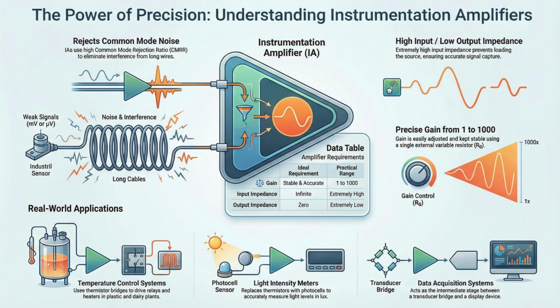And this is where your argument for survival over precision kind of falls apart. A bridge circuit has a very specific output resistance. If the IA doesn't have that extremely high input impedance, it acts as another resistor in parallel with the bridge legs. It unbalances the diamond. It creates a nonlinear error. You aren't just adding noise, you are warping the entire curve of the measurement. So if you're weighing a truck on a scale or measuring pressure in a pipe, that impedance mismatch means the scale reads 10% light. No amount of noise rejection fixes a lie that you told yourself at the input terminal.